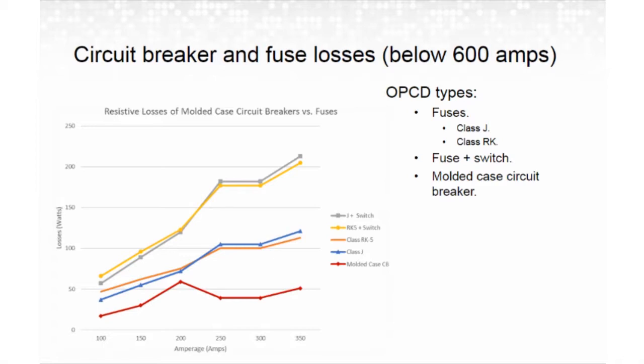So this graph illustrates power losses for overcurrent devices below 600 amps. It shows that fuses with switches, shown in gray and yellow up top, have the highest losses, and those losses predictably increase with current. Both type J and type RK5 fuses are represented here. The orange and blue lines in the middle illustrate the fuse contribution only and do not include the switch that typically accompanies a fuse. This is shown to identify that contribution so you can see how much of that large loss at the very top of the graph is really just from the fuse itself.